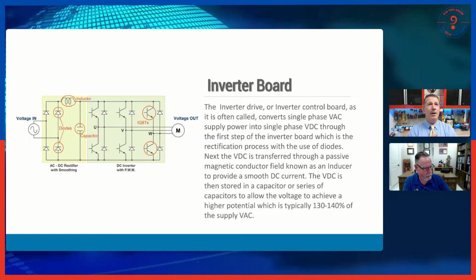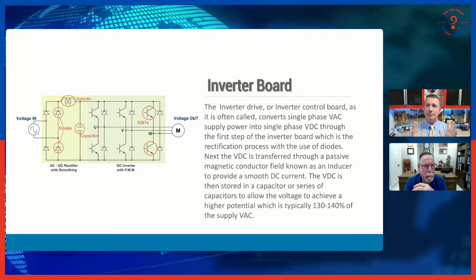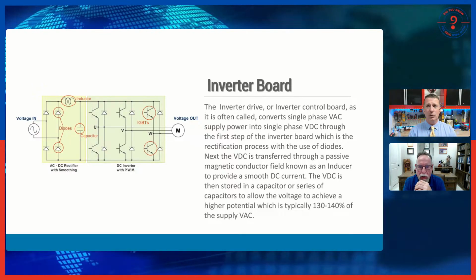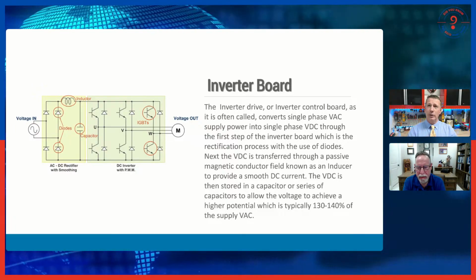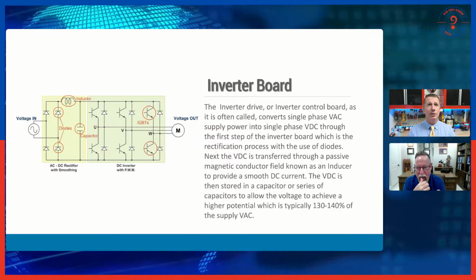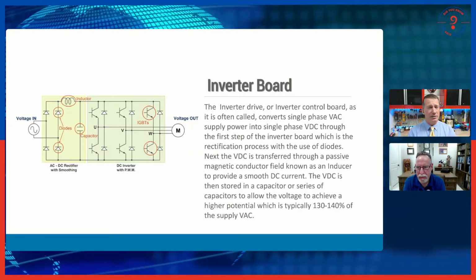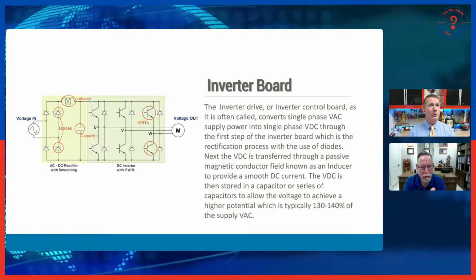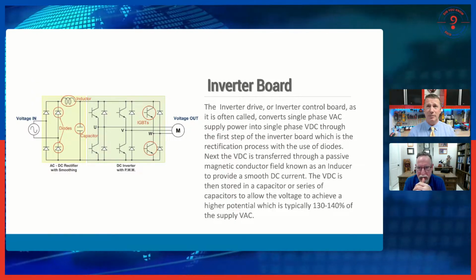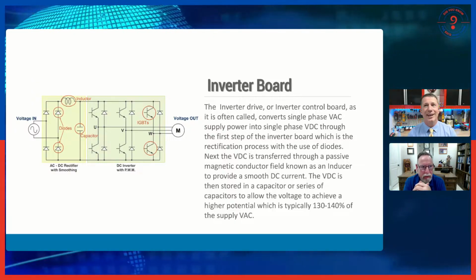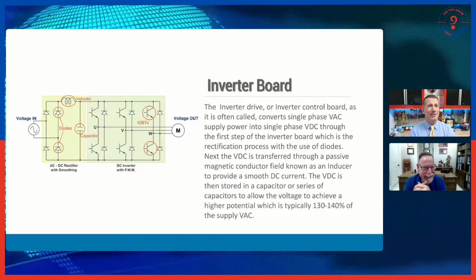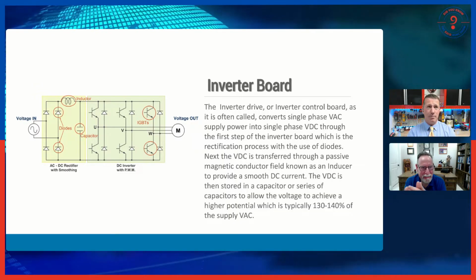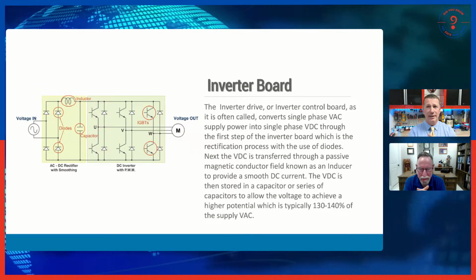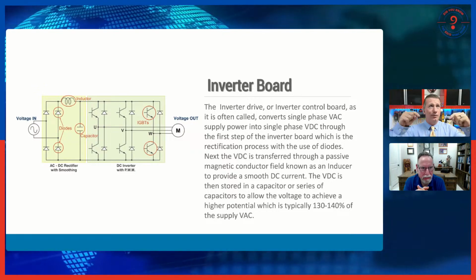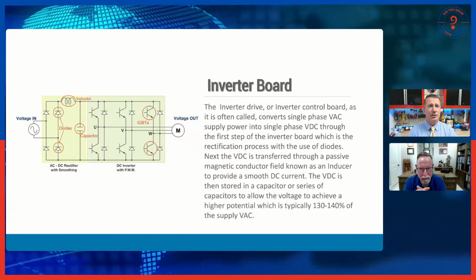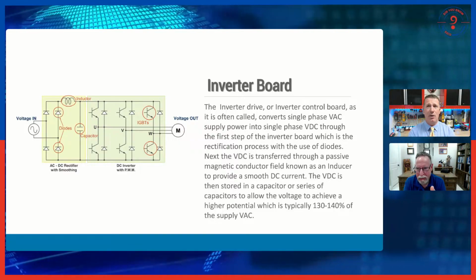So thinking about what's happening here, we understand the flow of high voltage. We should be able to check coming into that inverter control board - we'll have our standard line voltage. If I've got a 240 volt system and only 120 volts coming in, it's not the board, it's a power issue. Now what happens with that power once it gets into the board? That's one of the things we'll hopefully dive really deep into today, so you can see what's happening with that power.